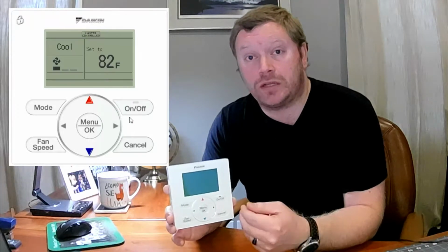And this is intentional. This is so that if this is installed on your wall, and you walk by, or the kids walk by and press a button, or you brush up against the NAV controller by accident, you don't turn your unit off or change it from heat to cool in the middle of the winter, or vice versa in the middle of the summer. So always make sure that the backlight is illuminated, it's on, before you press any of the buttons.